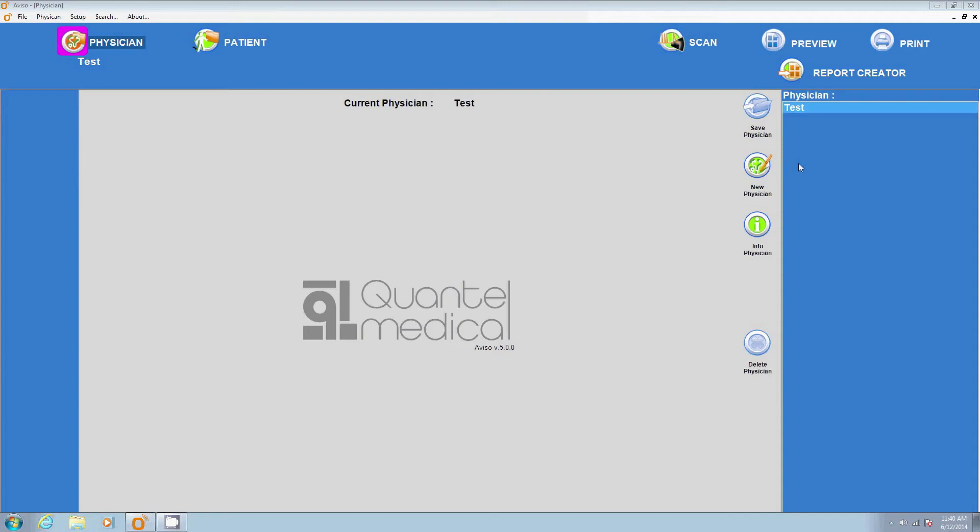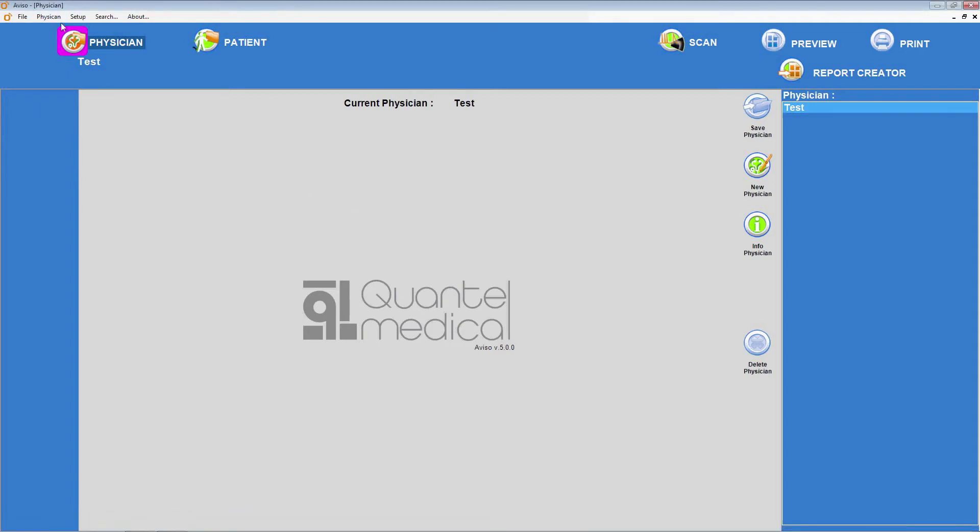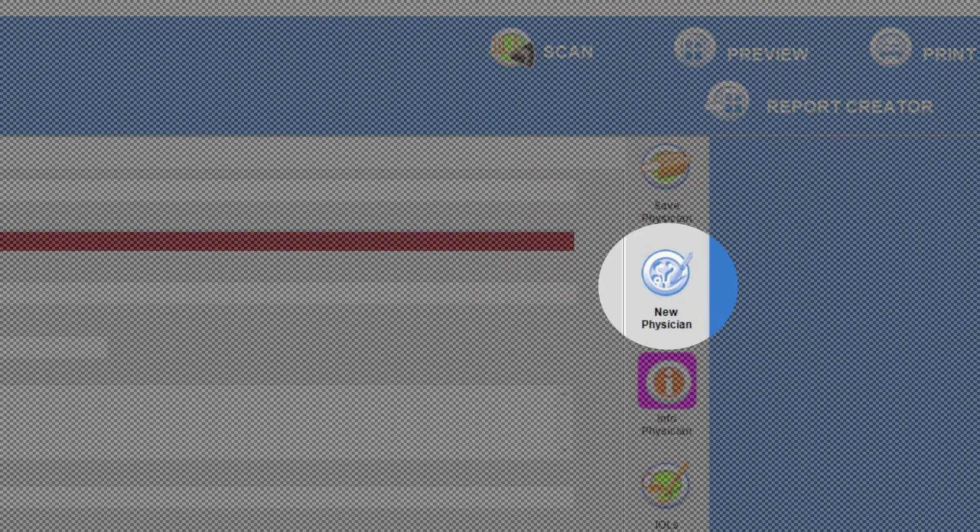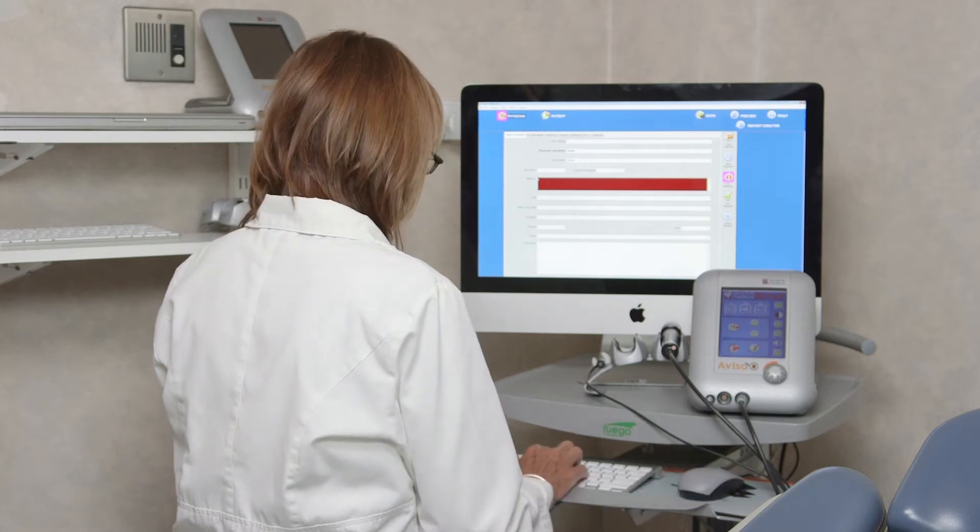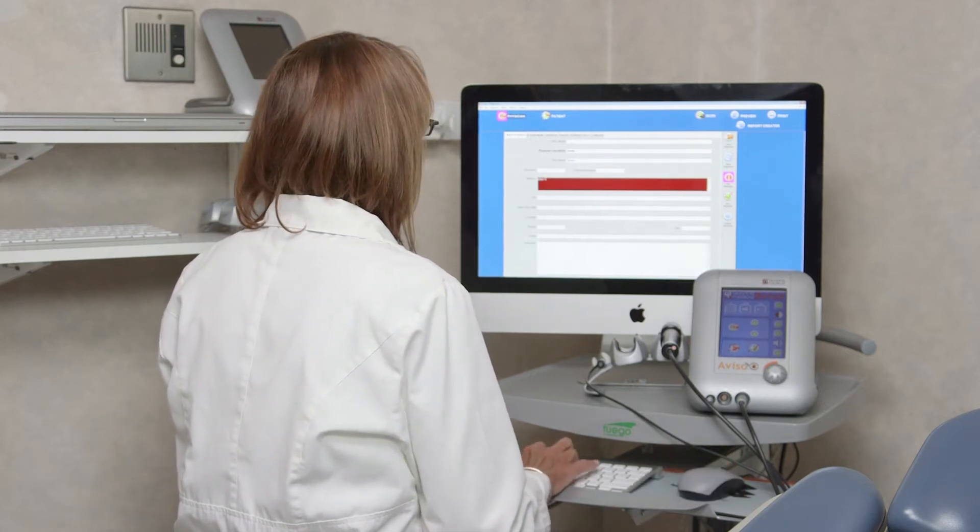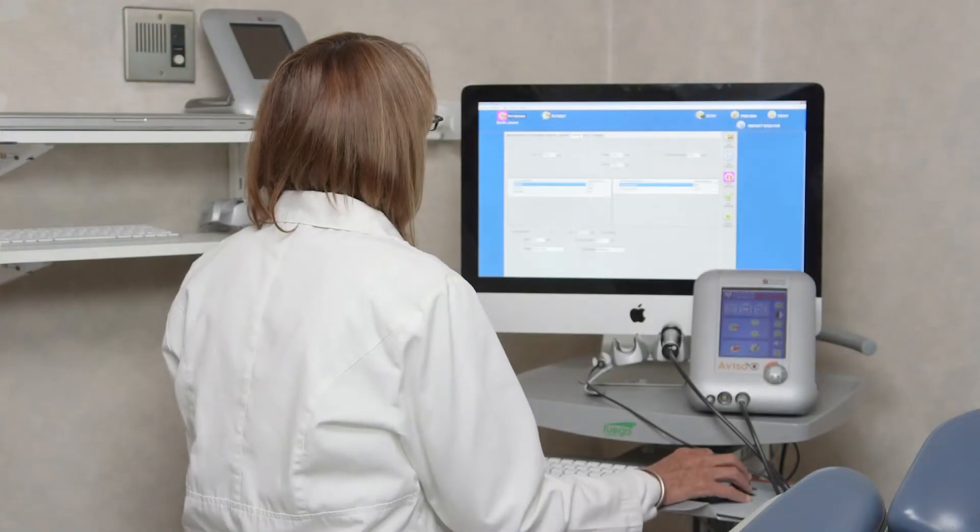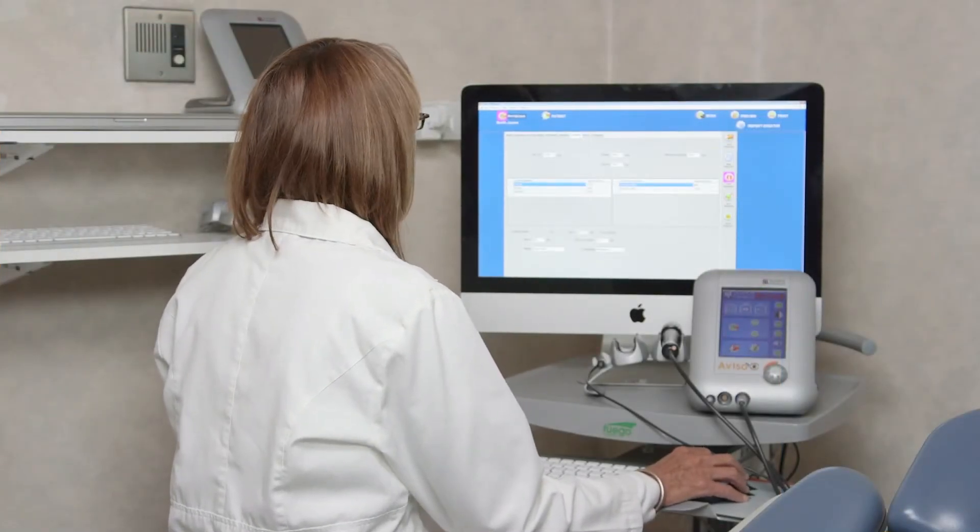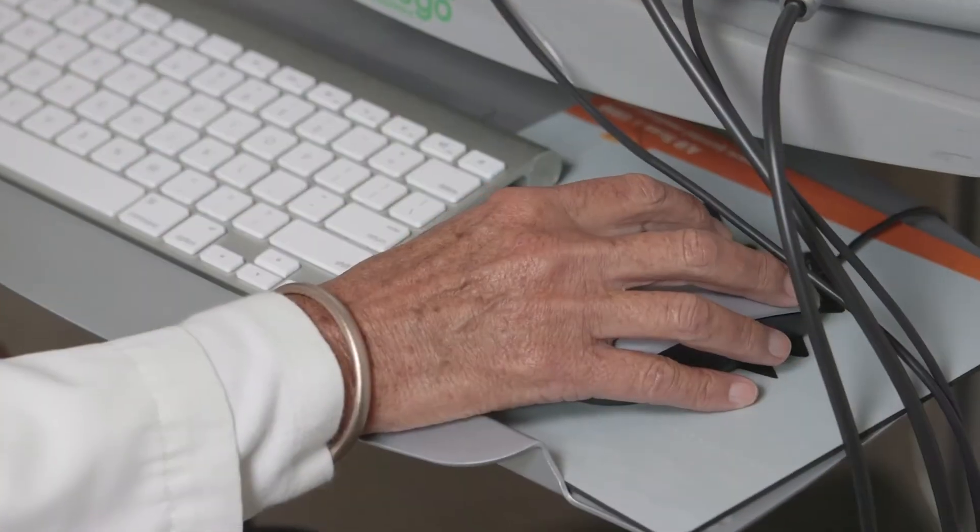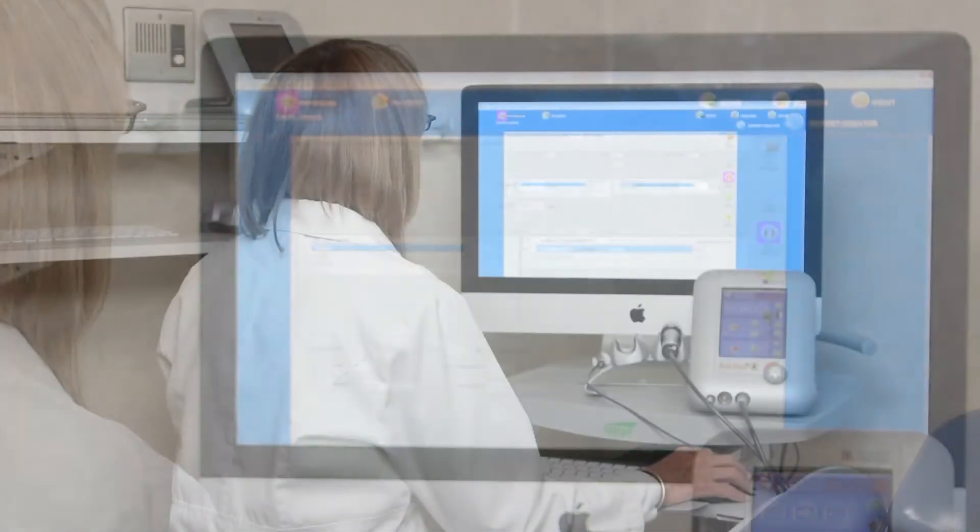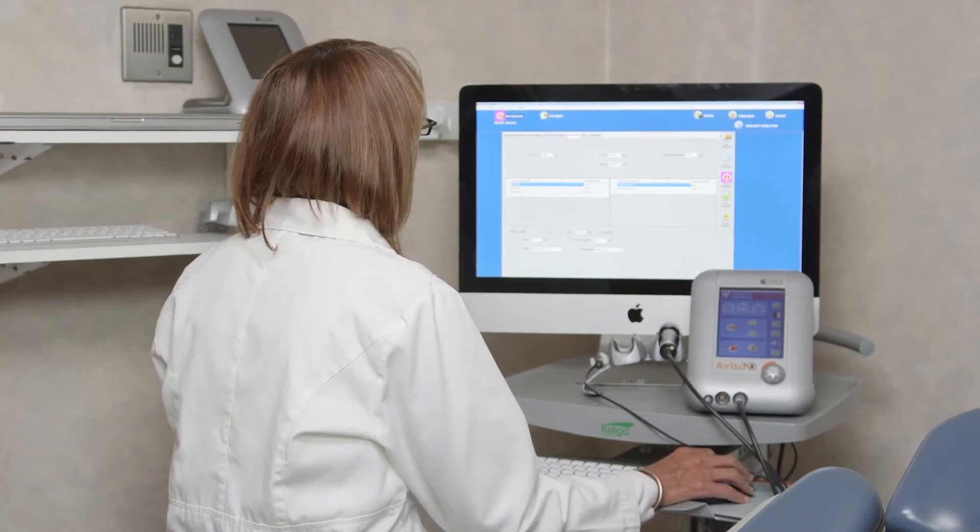Upon starting the Aviso software for the first time, the physician file screen will be displayed automatically. Thereafter, selecting the New Physician icon will open up this menu. At least one physician profile must be entered in order to begin using the Aviso-S device. In addition to the physician's name and address, various default parameters can be set based on physician preferences. From this menu, default folders can be set for saving images in JPEG format, CineLoop files in AVI format, and reports in PDF format, and a default length up to 40 seconds of CineLoop recording can be established. Certain particulars of reports, such as the number of images per sheet, specific notes or comments to be included, can be set from this menu as well.